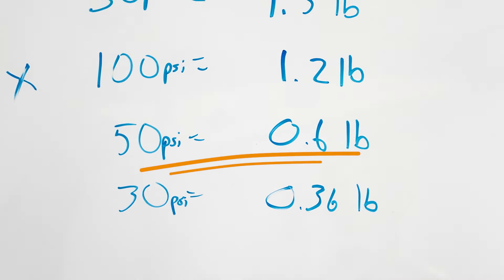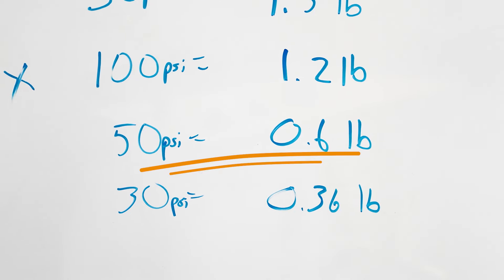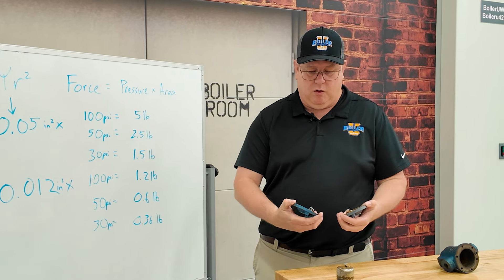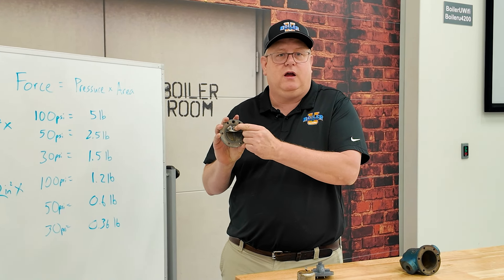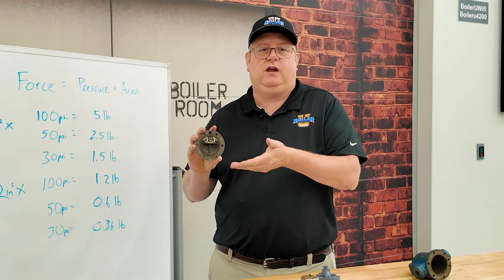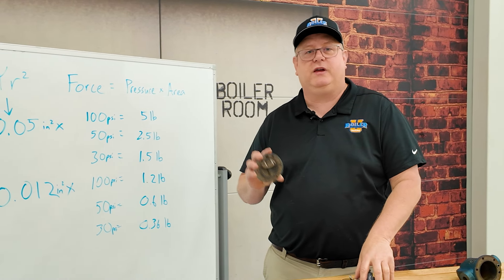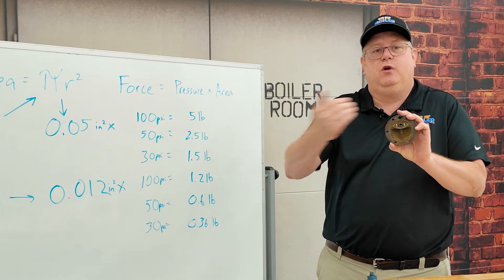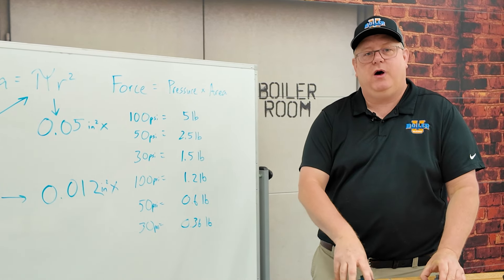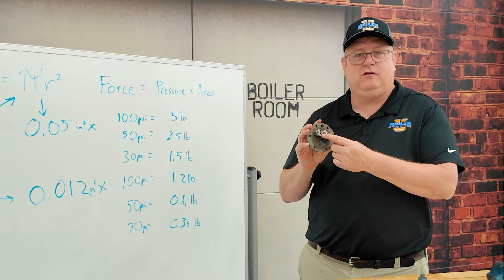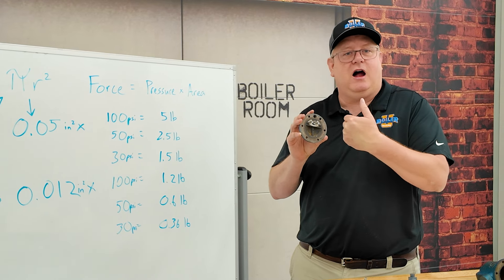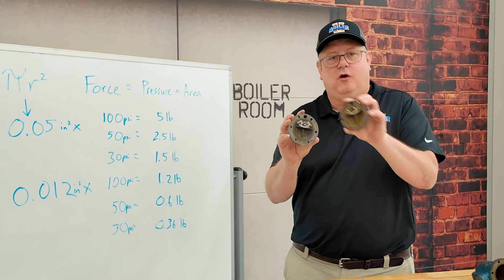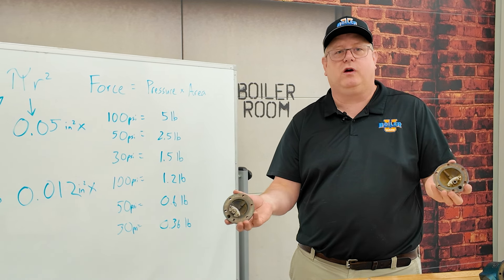I see eighth inch orifices on 100 PSI applications all the time and it works fine. So why don't we just use the smaller orifice on everything? Because we're going to lose capacity. On a low pressure application, we need a larger orifice so we can remove the condensate promptly. But on a higher pressure application, we can remove the same amount of condensate because we've got more differential. Having the right internal orifice is going to allow the trap to work correctly.